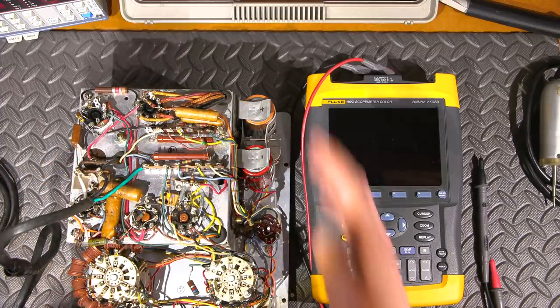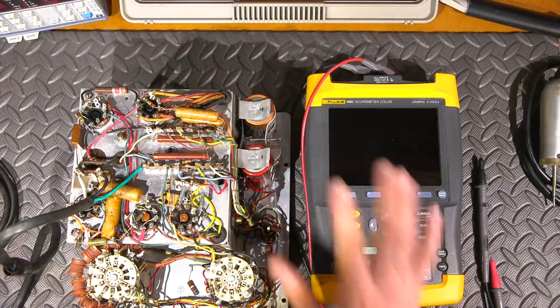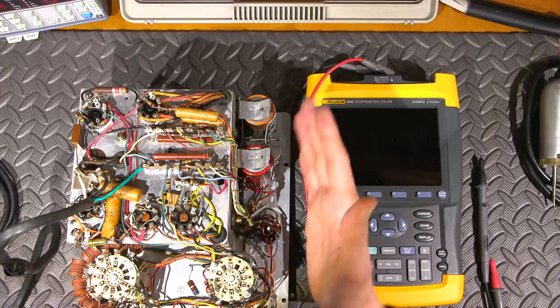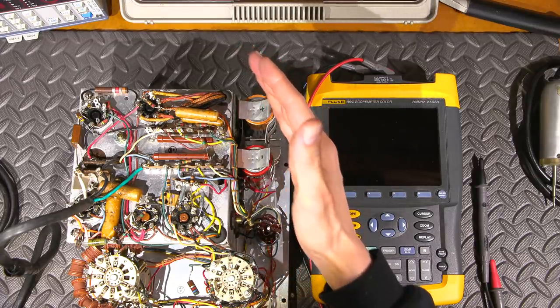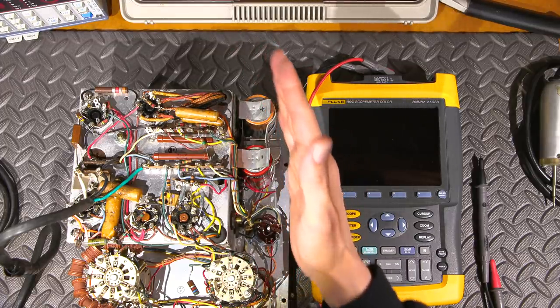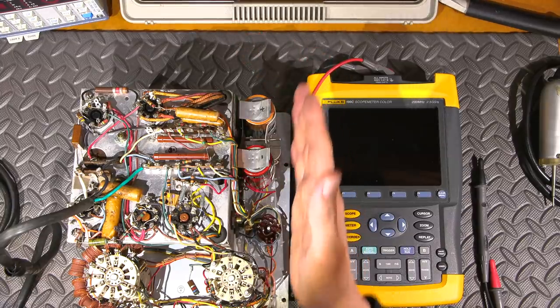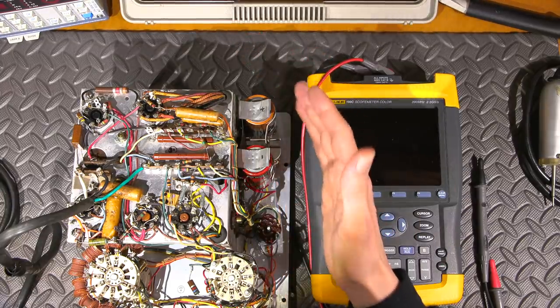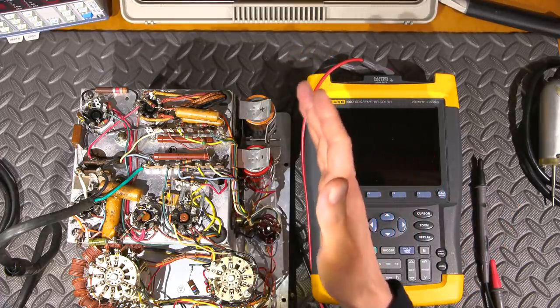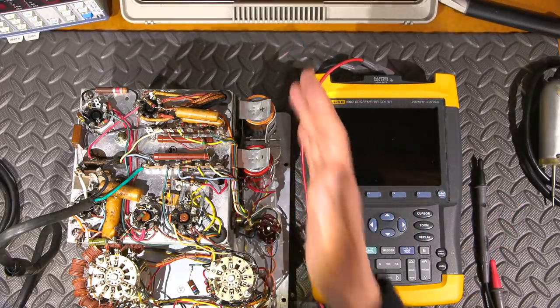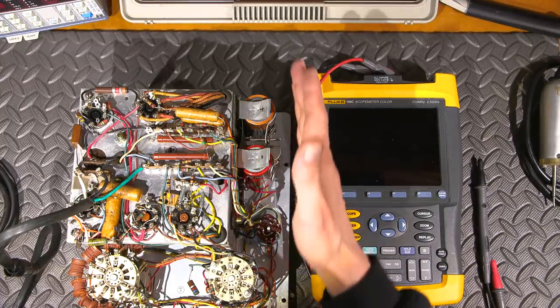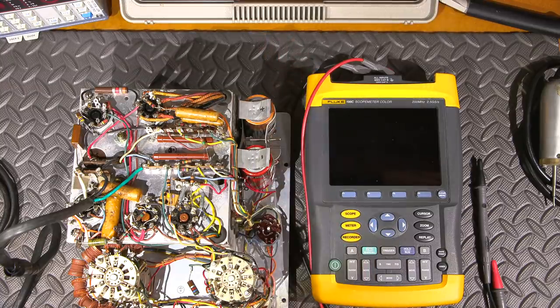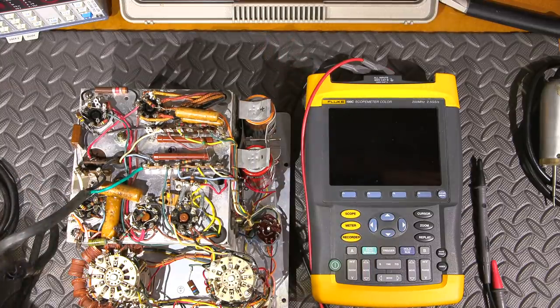For anything that you're working on where they have a portion of the line tied to the chassis, remember not all houses are wired correctly. So if your house is wired incorrectly, you know, it can make the case of this kind of hot. For all of you that have worked on these things before and you've rubbed your hand on the case and it feels like it's buzzing as you rub your hand on the case of a meter or an older piece of equipment. So you're just sitting there and you just touch the case and it feels like a buzzing sensation. Well, you know what that buzzing sensation is, right? You're isolated, you're not making a circuit, but you're feeling the AC on the case.